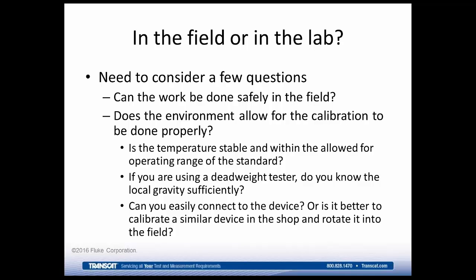So finally, that brings us to the question: how do we decide if we do our work in the field or in the lab? We need to consider a few questions. Can it be done safely in the field? And does the environment allow for the calibration to be done properly? Obviously, or one would hope, the environment that the device we're testing is installed in is appropriate for that device. But we also have to look at what environment is appropriate for our reference standard. It may only work under a much smaller temperature range, or we need to know local gravity for it. So is the environment appropriate for our calibration overall? Or are there wind drafts or other things that cause it to not be able to get a stable enough pressure to get a good reading from our reference?